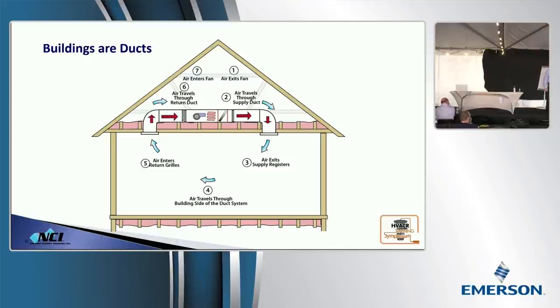We're trying to reduce that through thermal resistance and insulation. So as we look at these, those are the principles that we need on a duct system, right? Those same principles apply to a building. It needs to be tight. A lot of times builders say, well, the house needs to breathe. Great, where would you like me to knock the holes? You can't control air until you contain it. You got to seal it. It's the same thing with trying to balance a duct system that's leaking like crazy. You can't do it. You can't control ventilation. You can't control air changes in a building until you control the leakage rates. So those of you that are getting into building science, it ties in to combustion air as well. There is a direct correlation. As a matter of fact, some of the terms like stack effect come from that market.